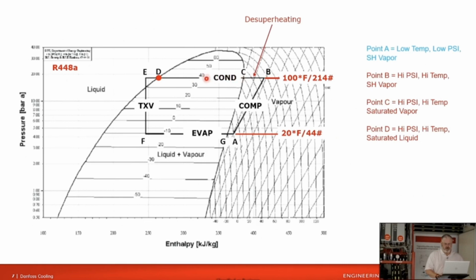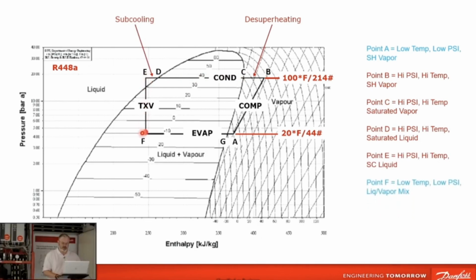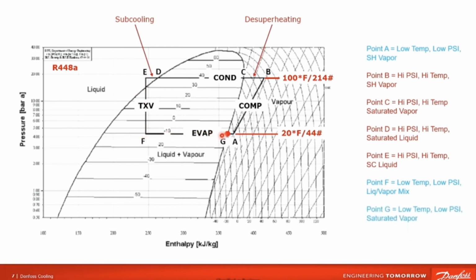We're condensing as we come through the condenser. In the last couple of passes, we'll subcool a little. And then we go across the expansion valve. So we went from high pressure, 214, down to evaporator pressure at 44 pounds. And then we go back through the evaporator. We boil all the liquid into a vapor. And then we superheat slightly before we go back into the suction of the compressor. So that's our basic refrigeration cycle.